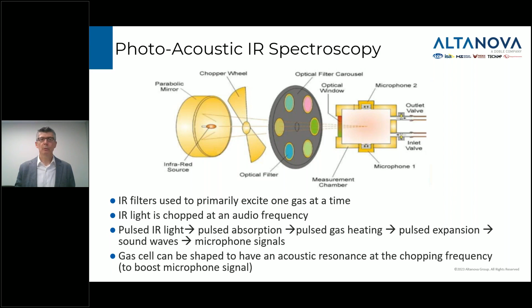So there are small, very sensitive microphones, typically on the sides of the gas cavity, that are able to pick up the sound of the IR light being absorbed by the gas. And that's why they call it photoacoustic. Typically, the chopper is running at an audio frequency, so the microphones can pick it up somewhere in the audio frequency range. And some of these systems have quite elaborate, optimized different shapes of gas cavities in order to maximize the amount of microphone signal for a given quantity of IR light and a given quantity of gas sample.